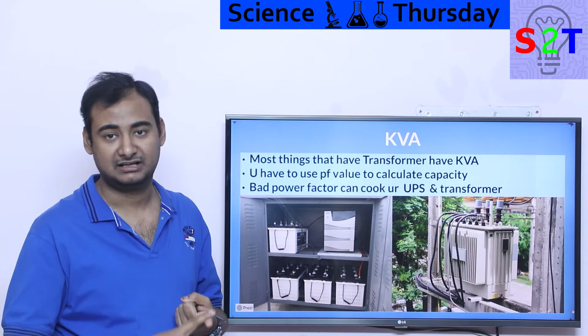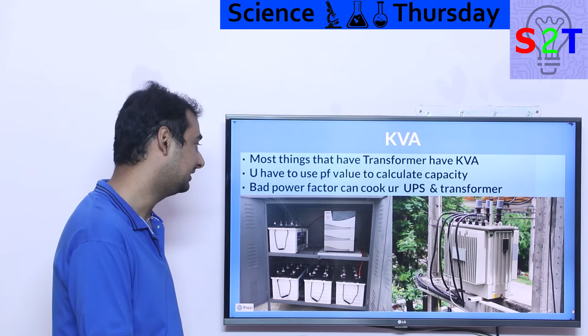Now this translates to the kVA reality that we live in. Basically everything that has a transformer, be it your UPS, be it your stabilizer, be it your main transformer, or even a generator, they are rated in kVA, and since the load is up to you, it's up to you to figure out the power loading for that. And if you have properly calculated the power factor, you will know how good it is.